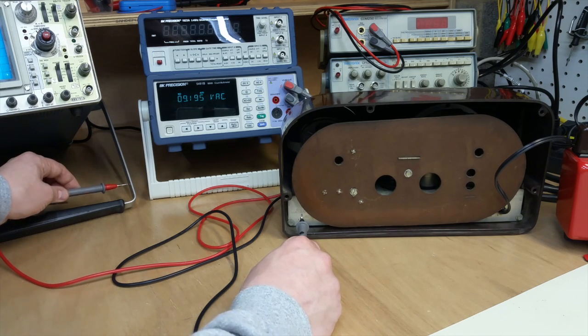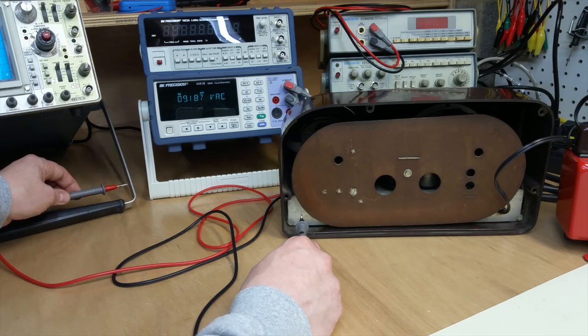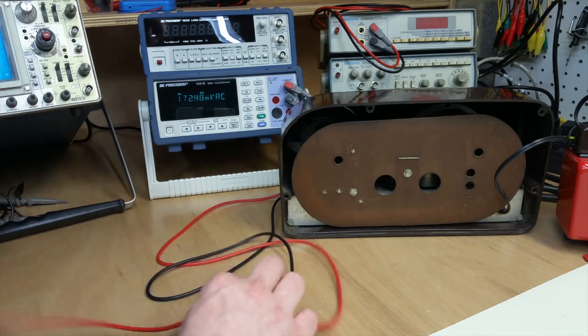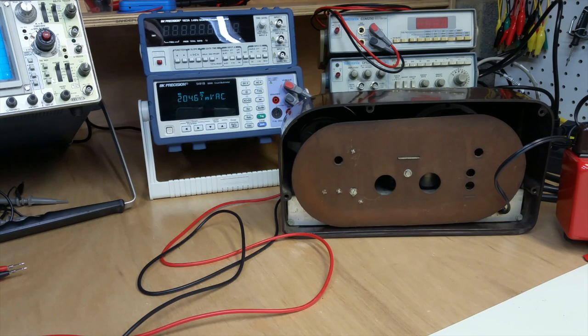This reading is what's called a ghost voltage. And it's not real. It is due to current that is coupled in to the stray capacitance of my probe cables and other parts of the circuit that are connected to the probes. The important thing about ghost voltage is that they do not carry significant current. And in fact, you can make them disappear by using a multimeter that has a low impedance setting. Some models of multimeters have a low Z setting, or by using a meter that is itself very low impedance, like an old VOM. If I were to measure this with an old Triplett VOM that I've got, which has a 10 kiloohm per volt sensitivity, it wouldn't budge at all. It would show a reading of zero volts.